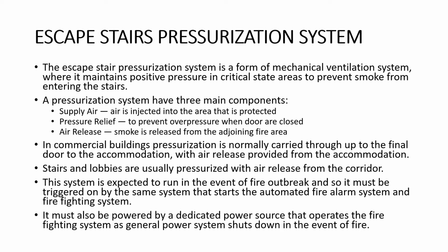Normally in commercial buildings, pressurization is carried through up to the final door to the accommodation, with air release provided from the accommodation. Stairs and lobbies are usually pressurized with air release from the corridor. The system is expected to run in the event of fire outbreak, and so it must be triggered by the same system that starts the automated fire alarm system and firefighting system. It must also be powered by a dedicated power source that operates the firefighting system, as the general power system shuts down in the event of fire.